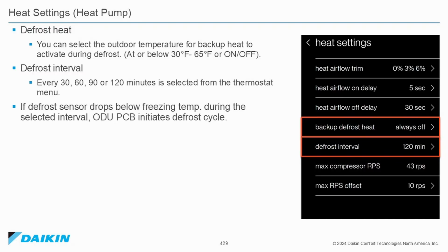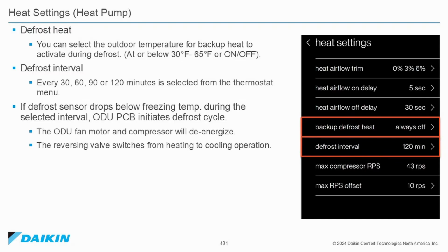If the defrost sensor drops below the freezing temperature during the selected interval, the outdoor unit printed circuit board initiates defrost cycle. The outdoor fan and compressor will de-energize. The reversing valve switches from heating to cooling operation. The outdoor printed circuit board communicates to energize backup heat if enabled.